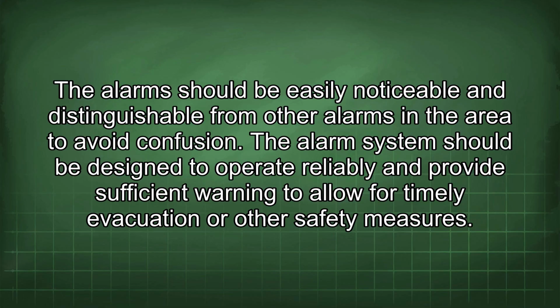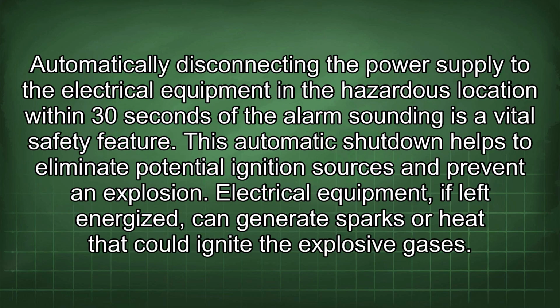The alarm system should be designed to operate reliably and provide sufficient warning to allow for timely evacuation or other safety measures. Automatically disconnecting the power supply to the electrical equipment in the hazardous location within 30 seconds of the alarm sounding is a vital safety feature. This automatic shutdown helps to eliminate potential ignition sources and prevent an explosion.